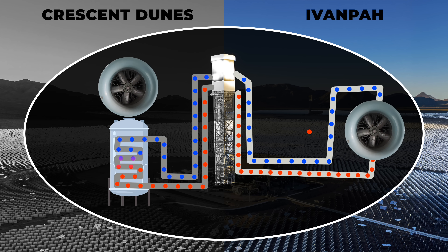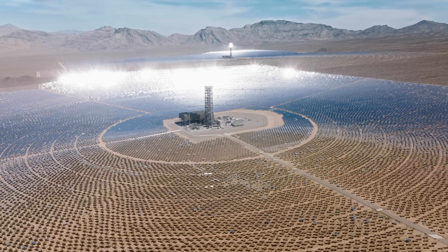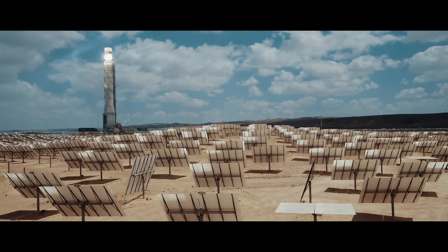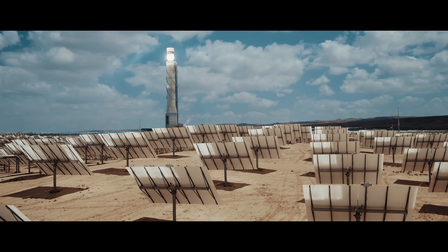This is very different from the Crescent Dunes design, which had a tower of hot molten salt that ran through a heat exchanger to produce steam and then run the turbine. In many ways, Ivanpah was simpler, although the steam could only reach temperatures of about 510 degrees Celsius. Crescent Dunes operated at much higher temperatures — almost 600 degrees Celsius — thanks to its molten salt formulation.